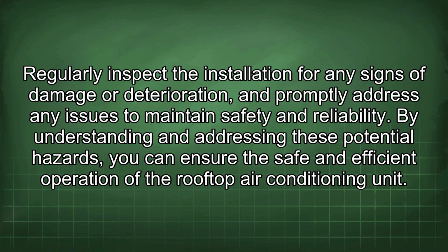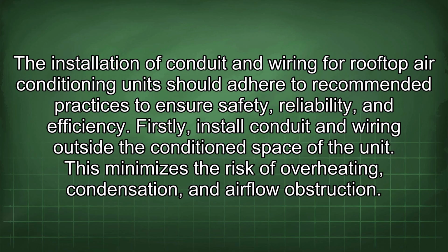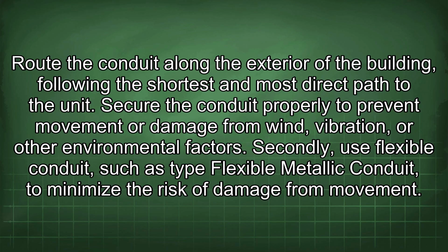The installation of conduit and wiring for rooftop air conditioning units should adhere to recommended practices to ensure safety, reliability, and efficiency. Firstly, install conduit and wiring outside the conditioned space of the unit. This minimizes the risk of overheating, condensation, and airflow obstruction. Route the conduit along the exterior of the building, following the shortest and most direct path to the unit. Secure the conduit properly to prevent movement or damage from wind, vibration, or other environmental factors.